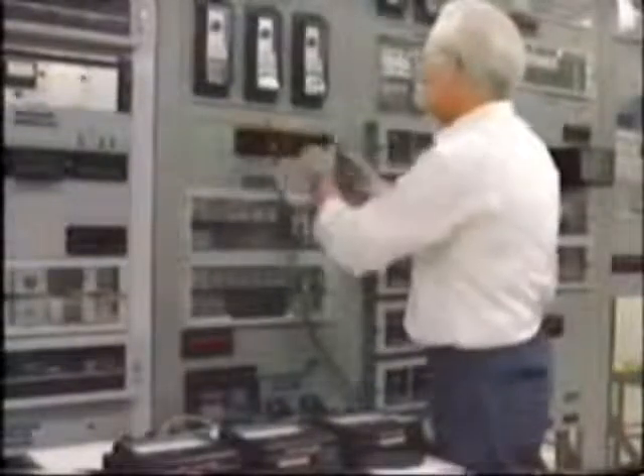When measuring currents in this live circuit, analog ammeters with less than 1% error are being used. Multimeter use is not recommended in this situation. Ensure that the accuracy level is suitable for the job.